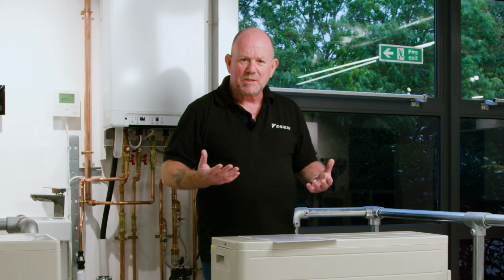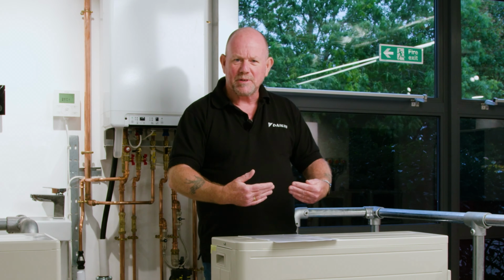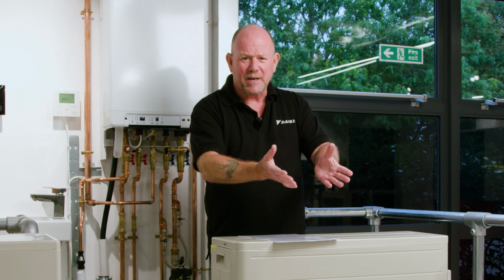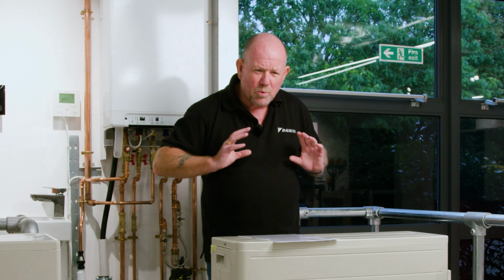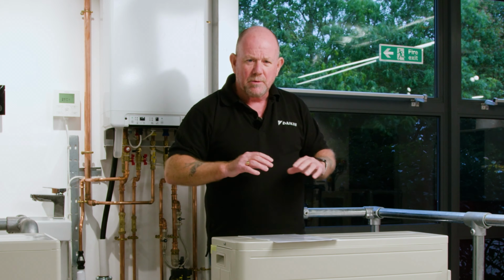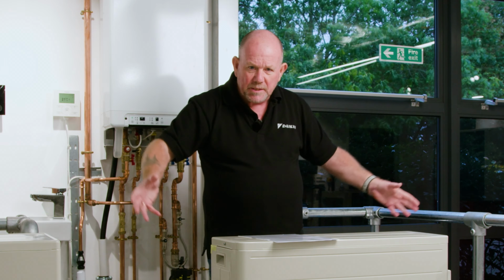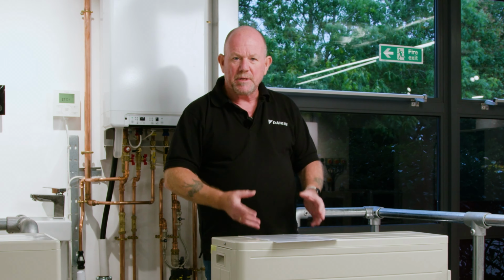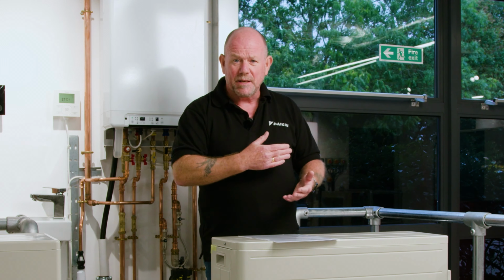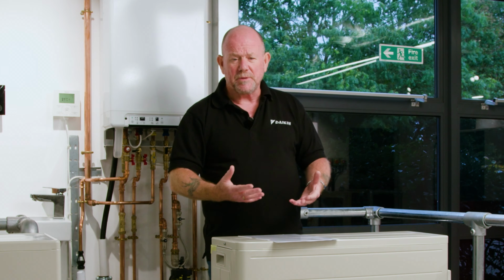On average, there's a 7 to 10 degree difference between the temperature of the air going onto the unit and the temperature of the air coming off. Think about an average winter's morning: if the air's going on at 5 degrees, it's actually coming off at -5. What we want to make sure is that that cold air disappears. What we don't want is that cold air to be recirculated back into the unit, because that's going to cause a drop-off in efficiency and a drop-off in the performance of the unit.